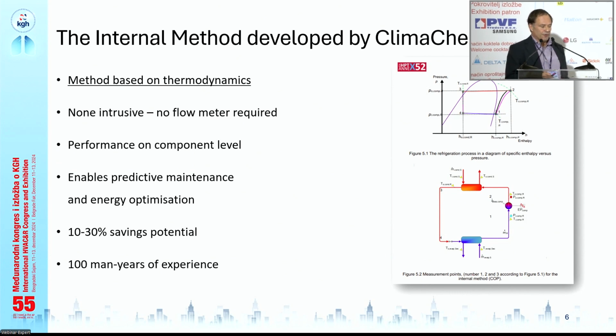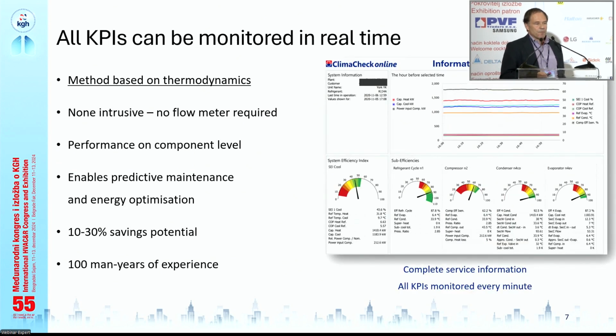There's a lot of discussion on COP, but COP is changing with every degree you change your temperature lift. It changes 2 to 5% depending on the system and if it's a high side or low side, but it changes a lot. And the systems are very dynamic, and they must be dynamic to be efficient. So if we instead look at the Carnot efficiency of a system working at exactly the conditions that we are operating now, then we can compare the Carnot COP with the COP that is measured. Then we get an efficiency versus a loss-free process. And we also see which component is causing the losses. So it becomes a very intuitive way of looking at systems.